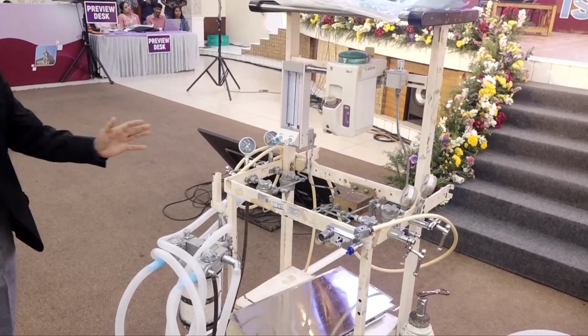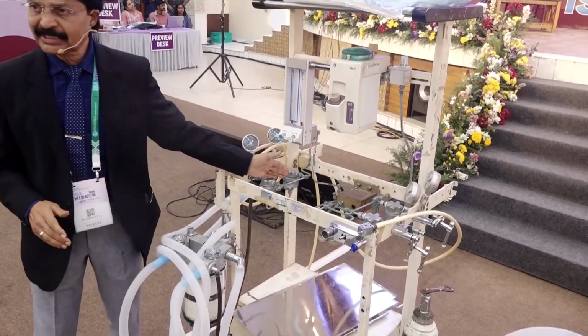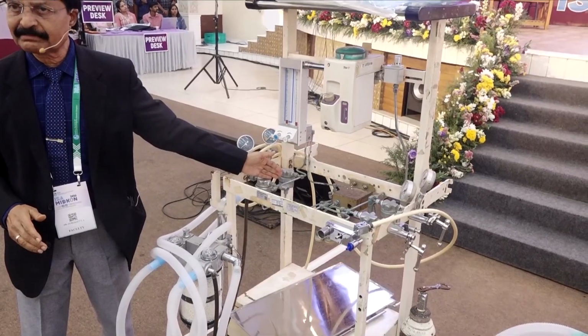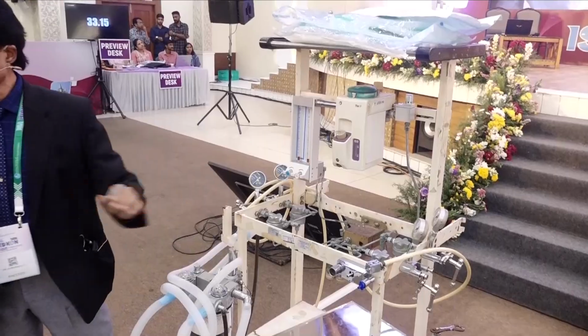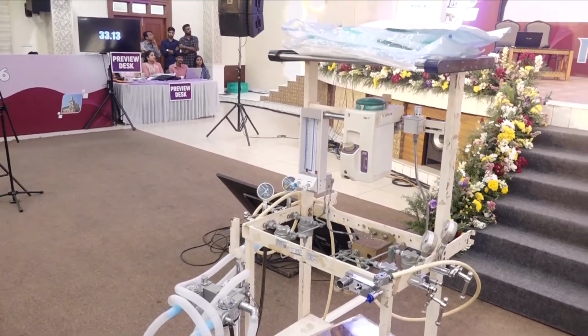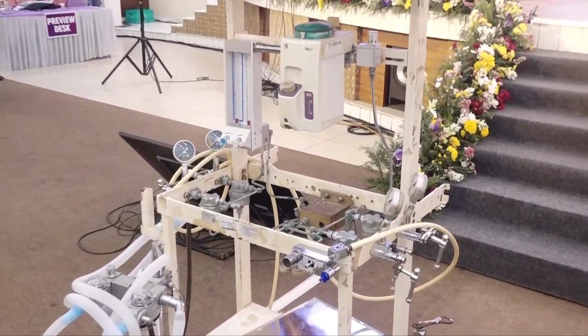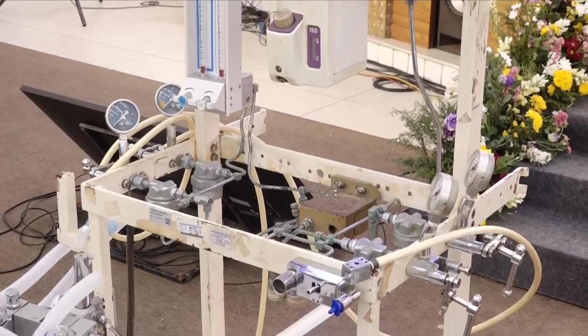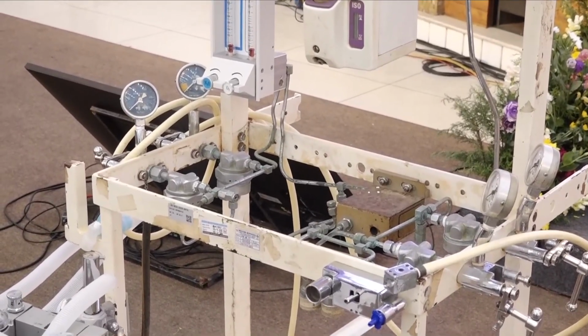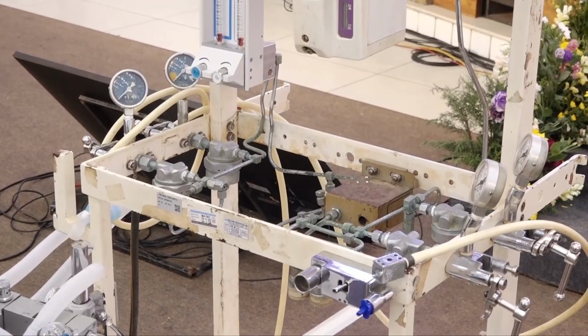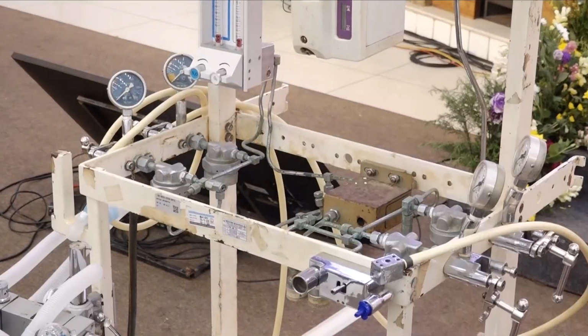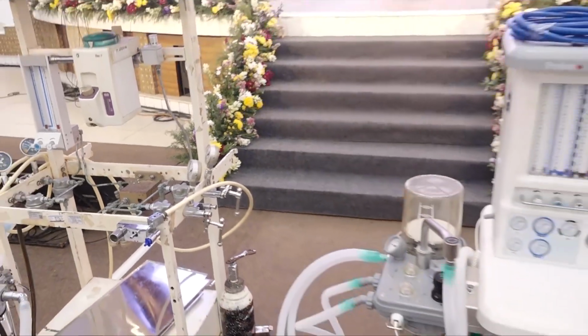After that, up to the pressure regulator, you have the high pressure circuit. The pressure regulators reduce the pressures of these cylinders to 45 pounds per square inch. From then onwards is the intermediate pressure system. In the modern workstations, we also have the pipelines connected to the intermediate pressure system.